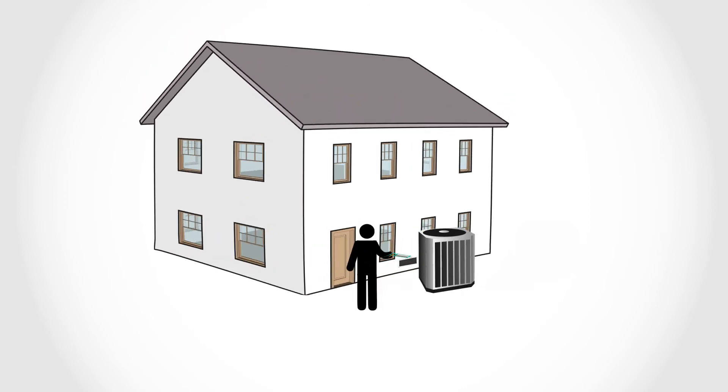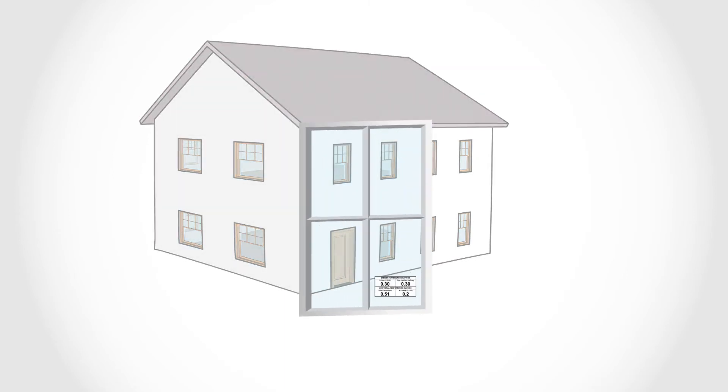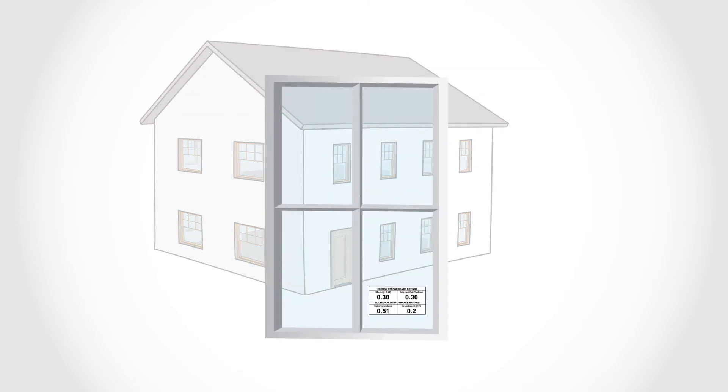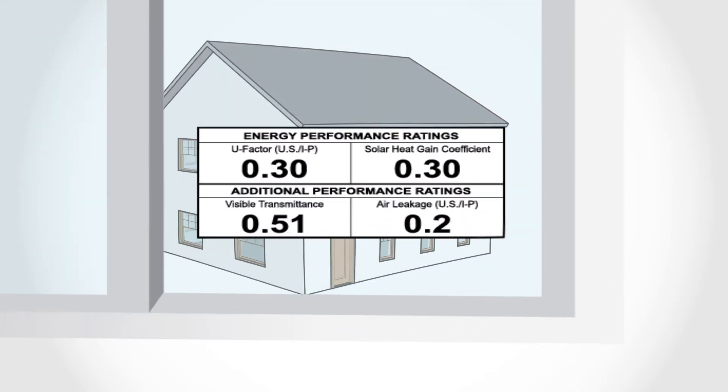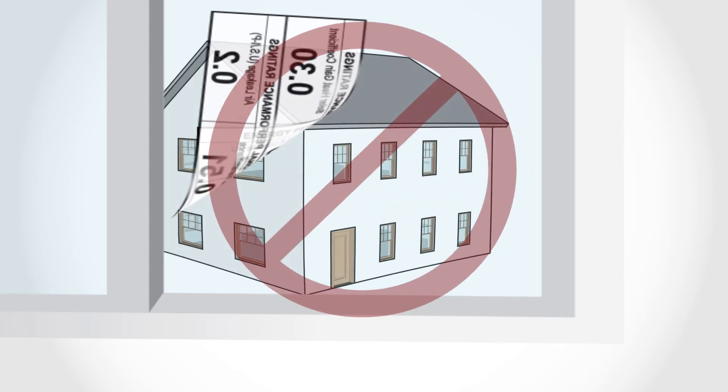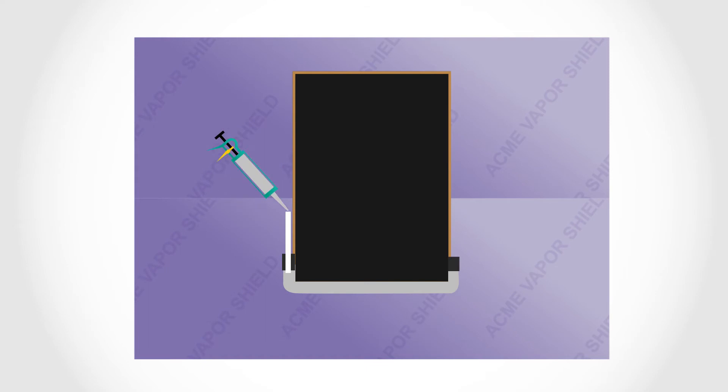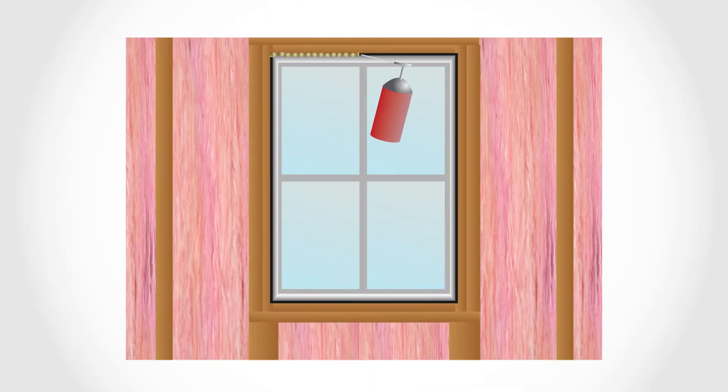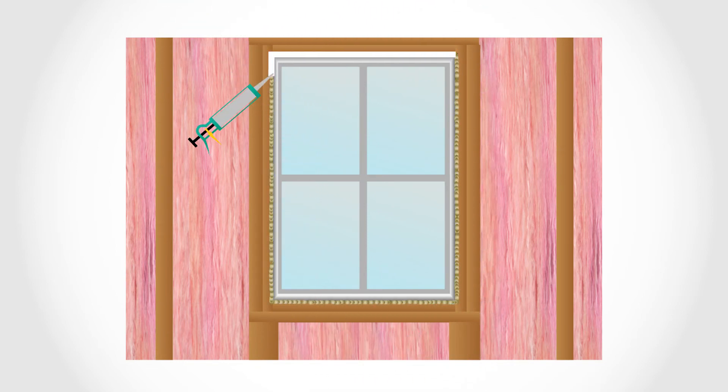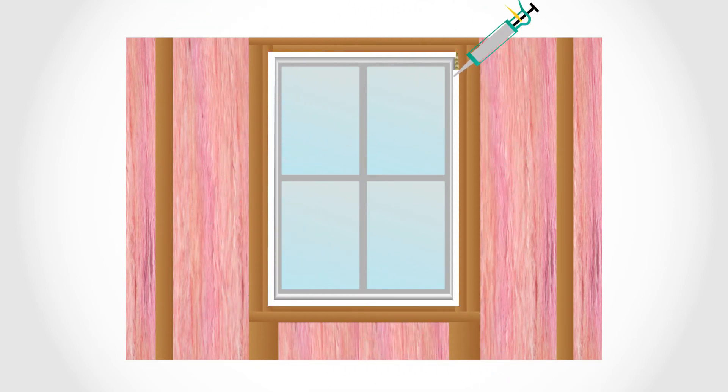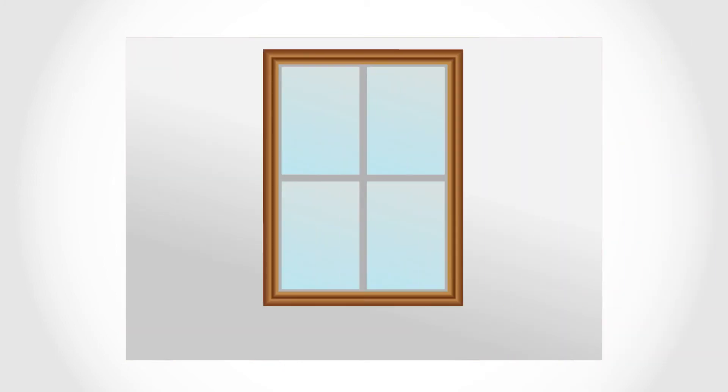New windows need to be factory rated with an air leakage of 0.3 cubic feet per minute or less. Each window should have an NFRC label with its rating. Don't remove these labels until all inspections are passed. When the window is installed, the installer must seal around the windows, seal the rough openings during construction, then caulk between the unit and the rough opening after installation. The interior window trim will provide the final layer of air sealing.